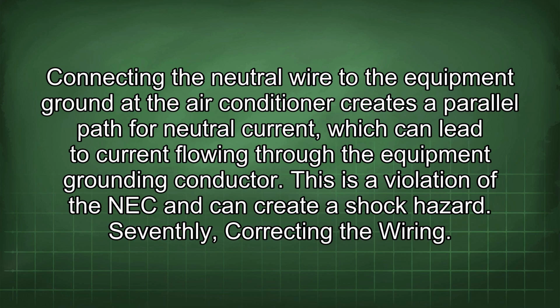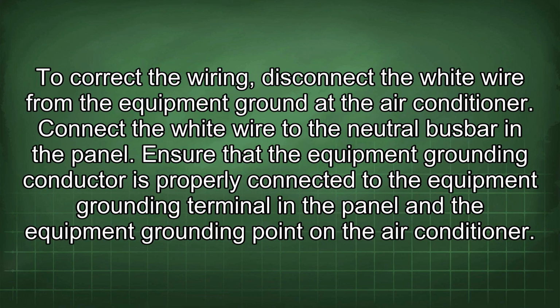Seventhly, correcting the wiring. To correct the wiring, disconnect the white wire from the equipment ground at the air conditioner. Connect the white wire to the neutral busbar in the panel. Ensure that the equipment grounding conductor is properly connected to the equipment grounding terminal in the panel and the equipment grounding point in the air conditioner.